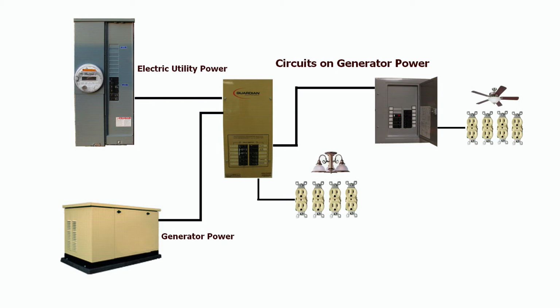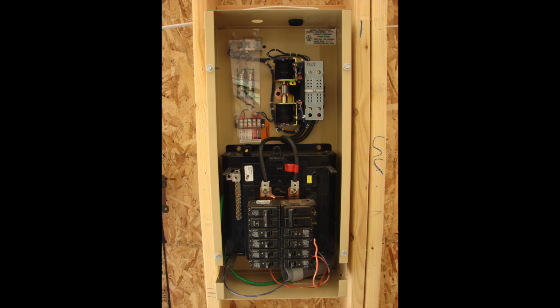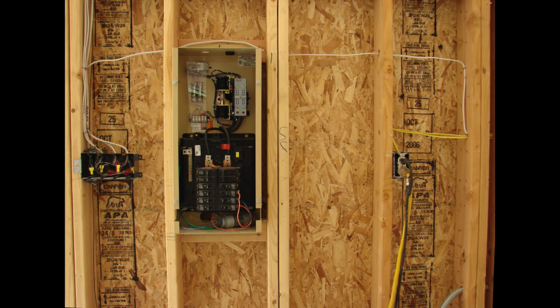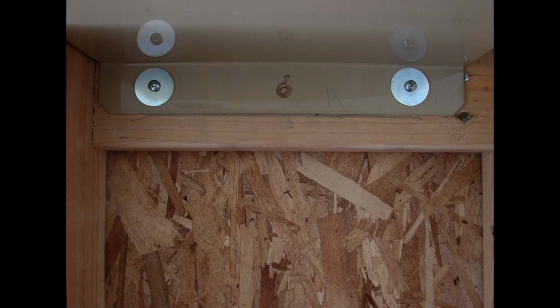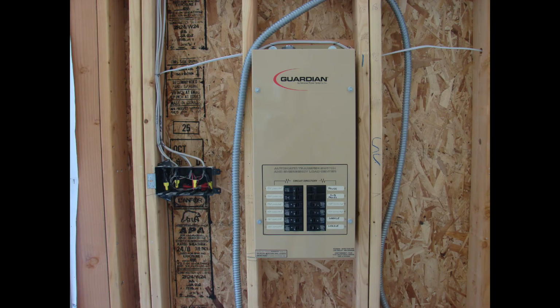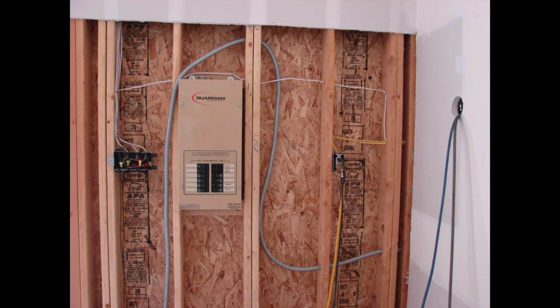So we begin by installing this transfer switch in an accessible location, of course. It's a pretty heavy panel, this particular one. It's 100 amp rated, so we have to put blocks in the wall. The wall's been opened up, so we put some stud cross pieces inside of the stud bay. We put the mounting screws in, and then we plan out our wiring. In this case, this transfer switch panel is about 15 or 20 feet away from the main panel, so it's not a great deal of a distance.